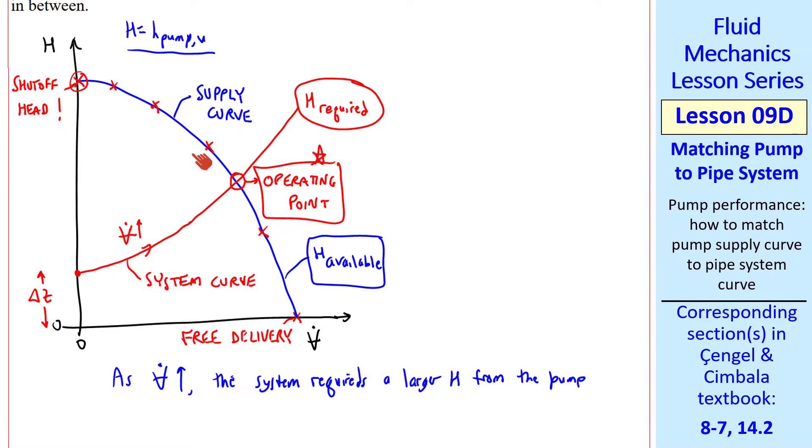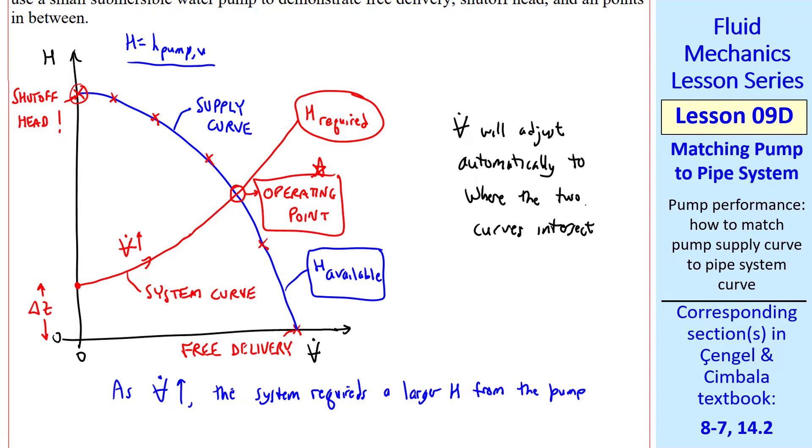You can also call this curve H required and you can call the blue curve H available. Regardless of what you call it, the flow will adjust itself so that it operates at this operating point. V dot will adjust automatically to where the two curves intersect, which is the operating point.